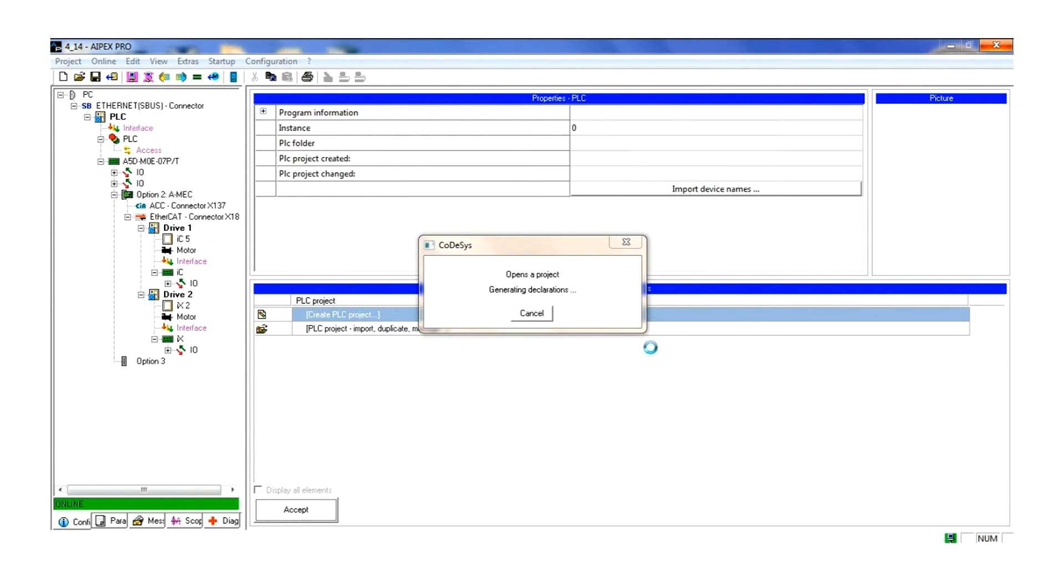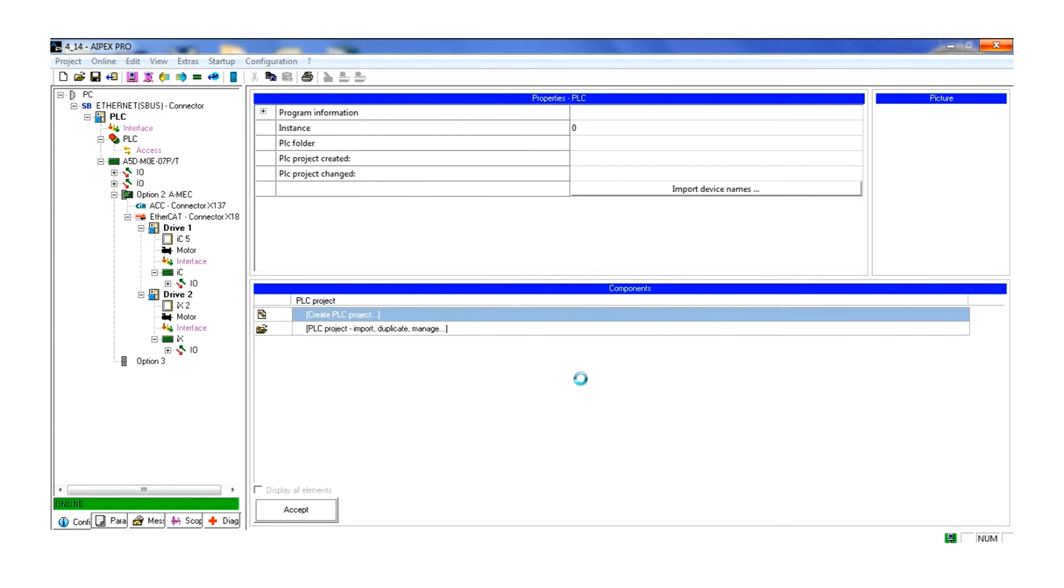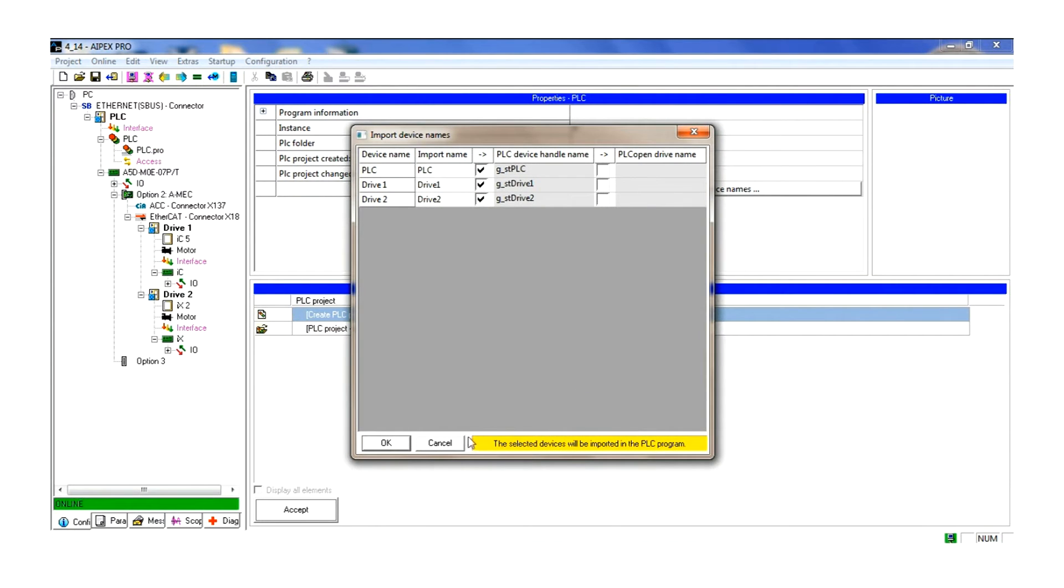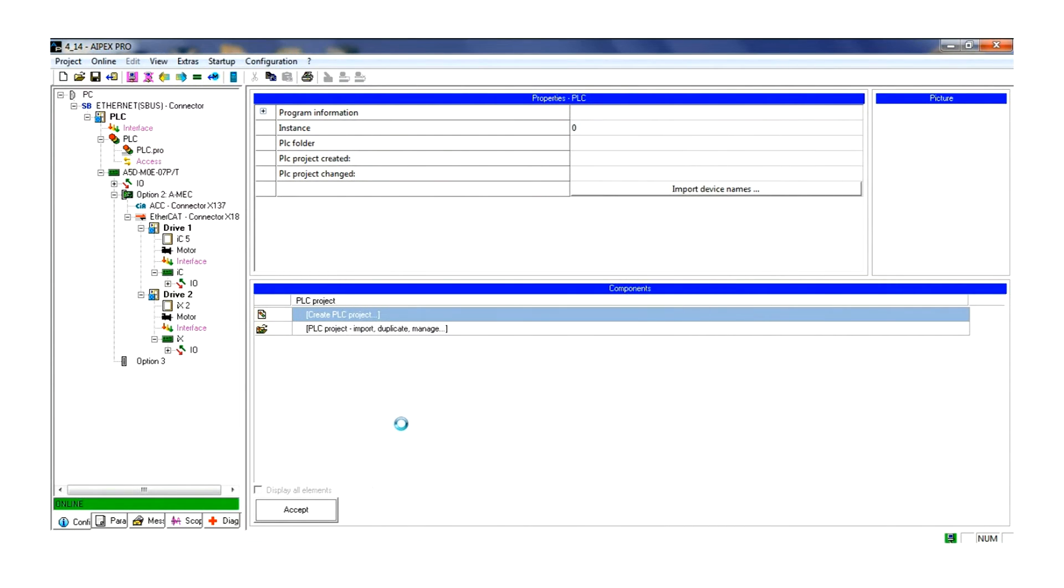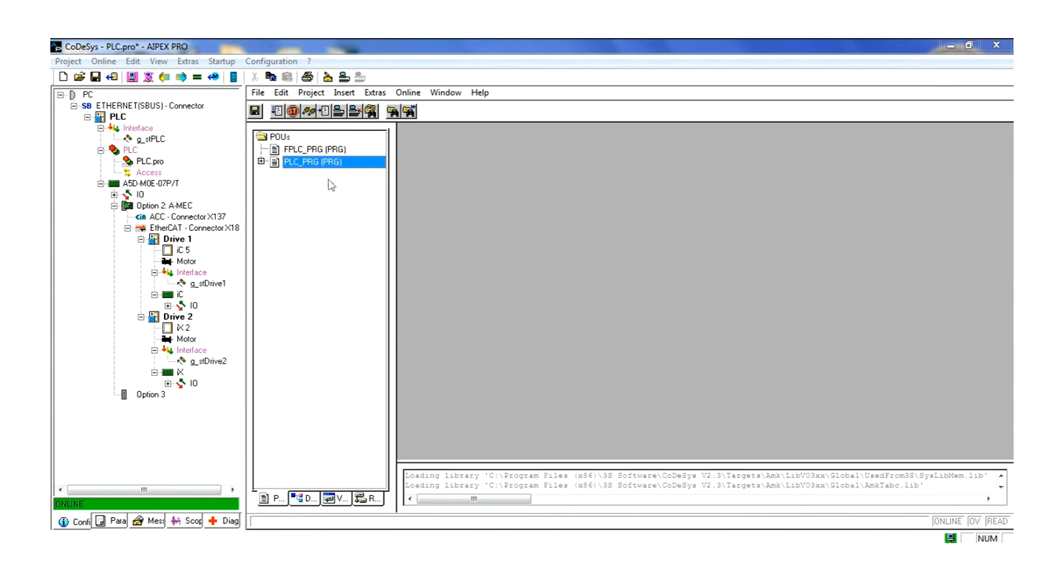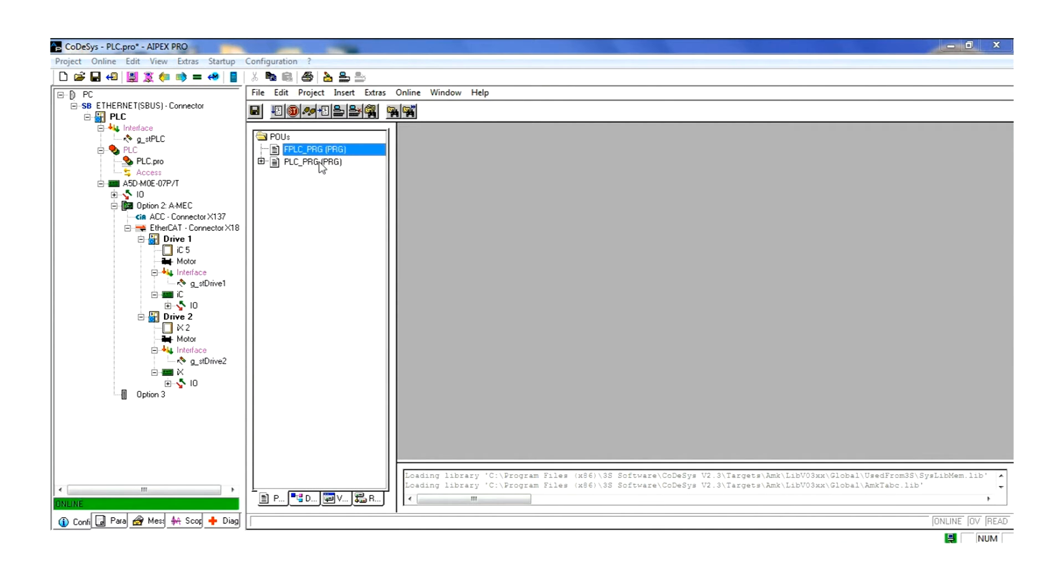Two separate program structures will be configured in the program. First is the PLC program. This is the main program and runs asynchronously. Second is the FPLC program. This is a synchronous portion of the program with a set cycle time.